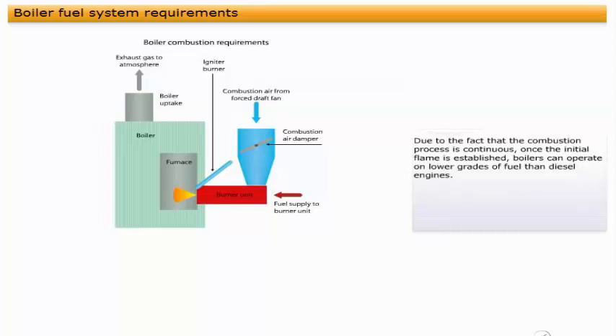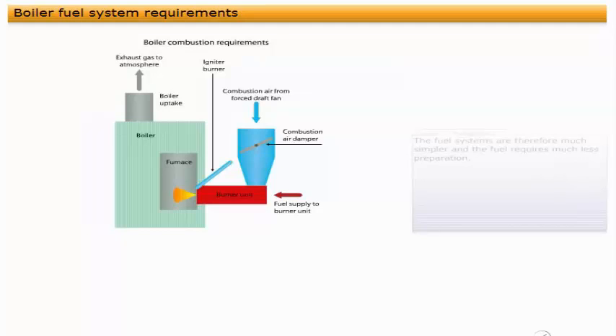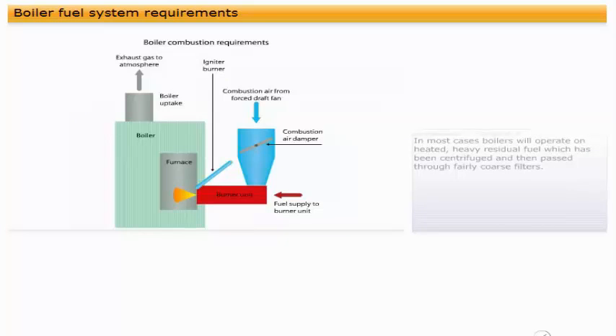Due to the fact that the combustion process is continuous once the initial flame is established, boilers can operate on lower grades of fuel than diesel engines. The fuel systems are therefore much simpler, and the fuel requires much less preparation. In most cases, boilers will operate on heated, heavy residual fuel which has been centrifuged and then passed through fairly coarse filters.